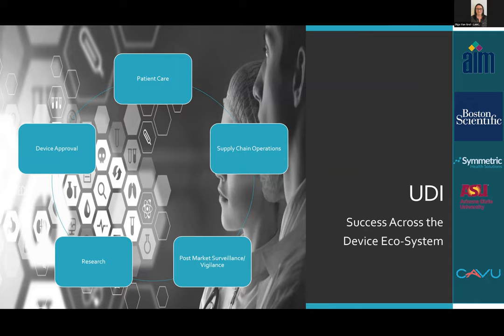includes a patient section written in language that's understandable to the layperson, and so on. The MDR also defines distinct economic operators in the supply chain. So you have the manufacturer, the importer, the distributor, who all play an integral role in compliance and the traceability of medical devices. The MDR includes trickle-down responsibilities in that each economic operator is checking that the upstream economic operator in the supply chain has met certain obligations and that the manufacturer has assigned UDI to devices.